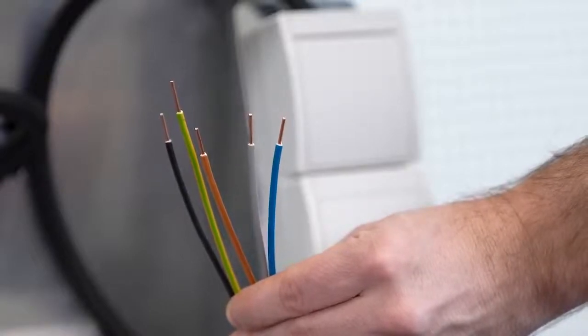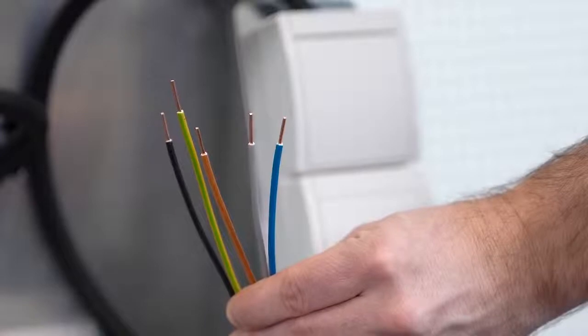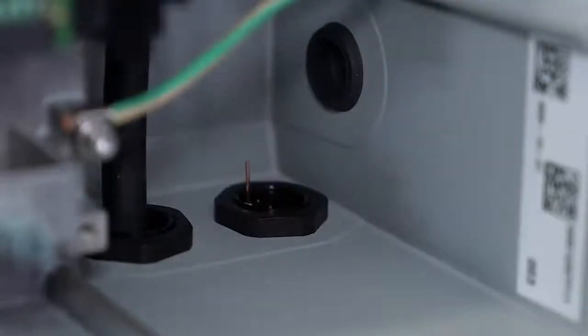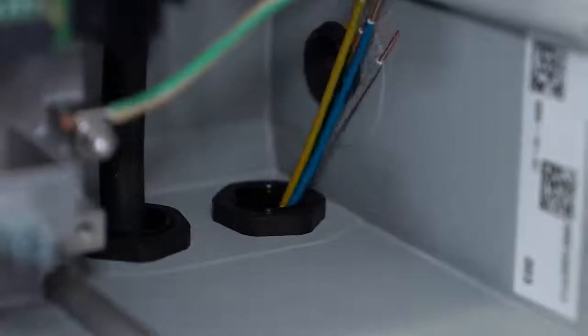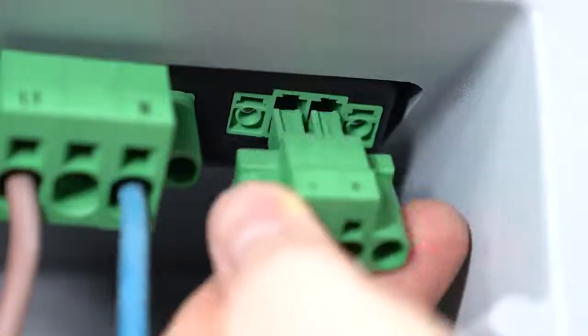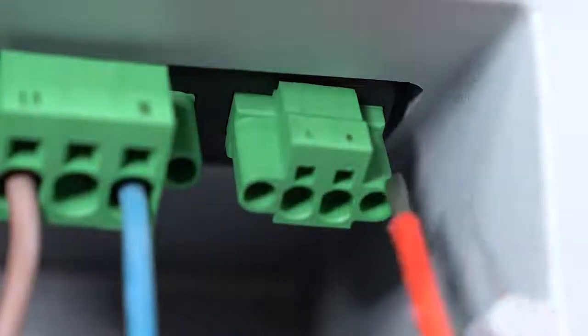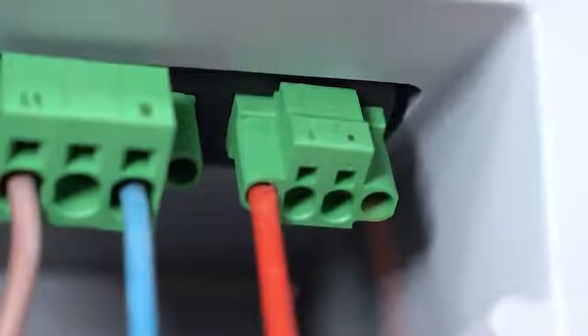In general, you need a three-wired cable for the AC secure power supply connection and one two-wire cable for the switch. In our example, I chose only one five-wired cable with the right cross-section to reduce wiring efforts. Please insert the cables through the intended cable gland and connect them to the plugs. Also here, connect the AC secure power supply plug to the inverter first. It should be tightened with a 3.5 mm flathead screwdriver.